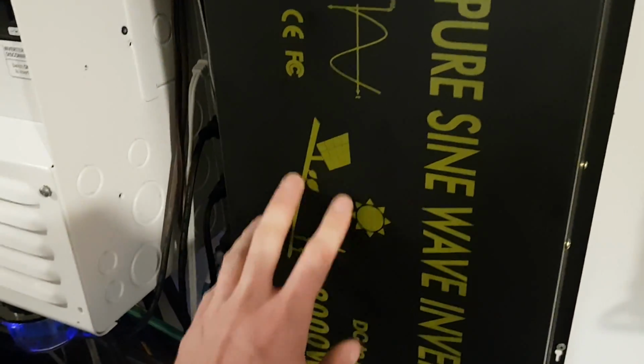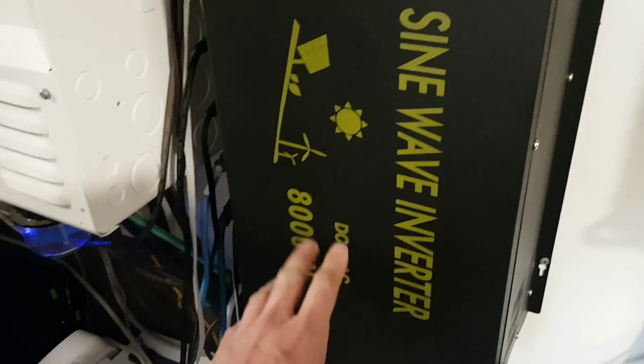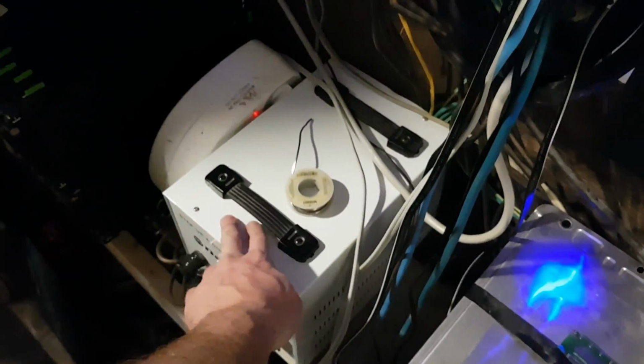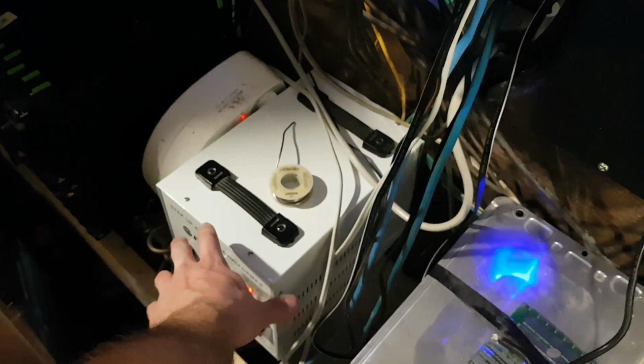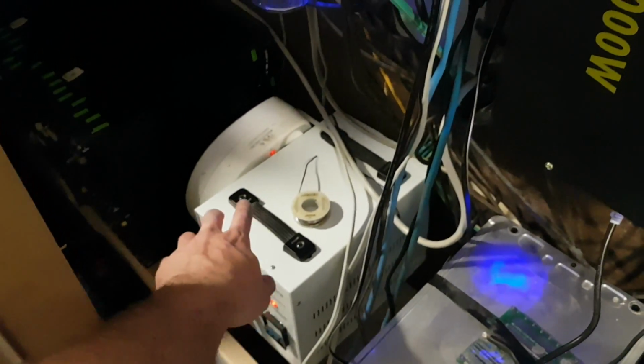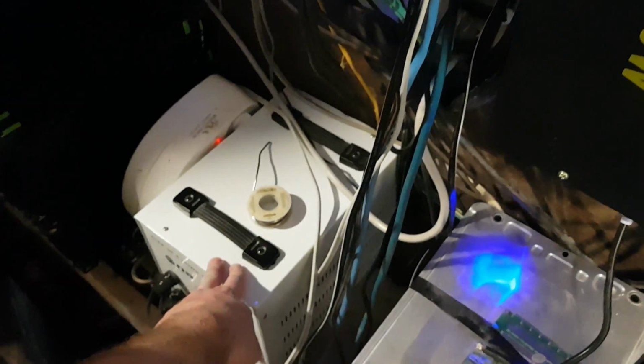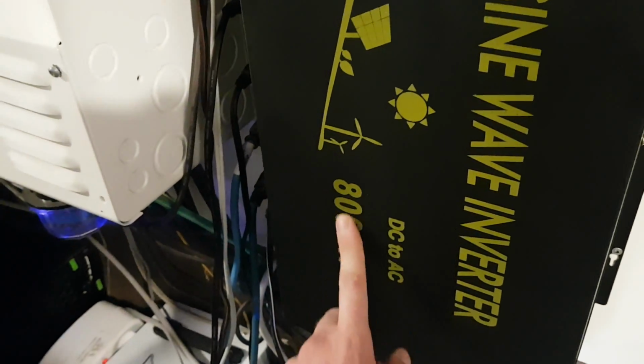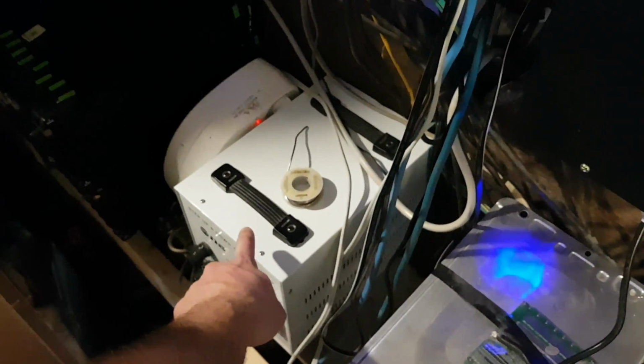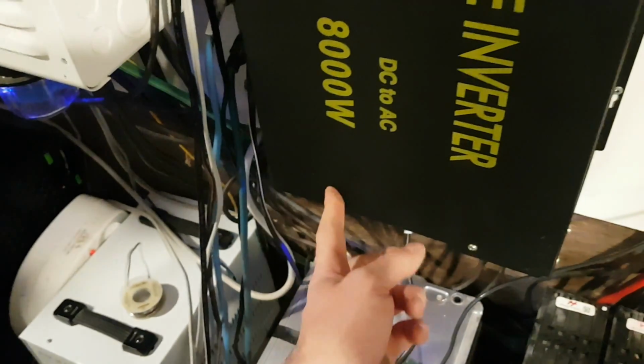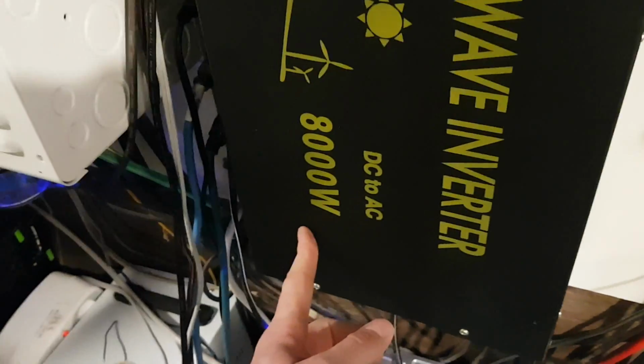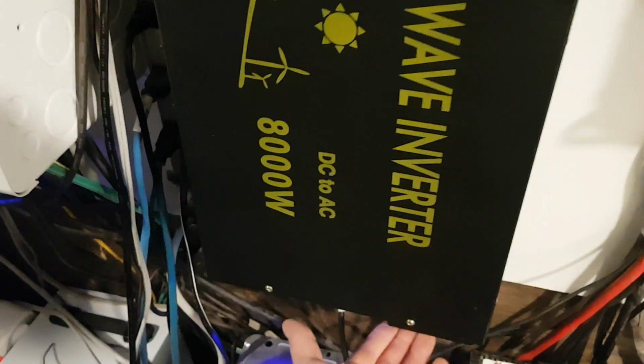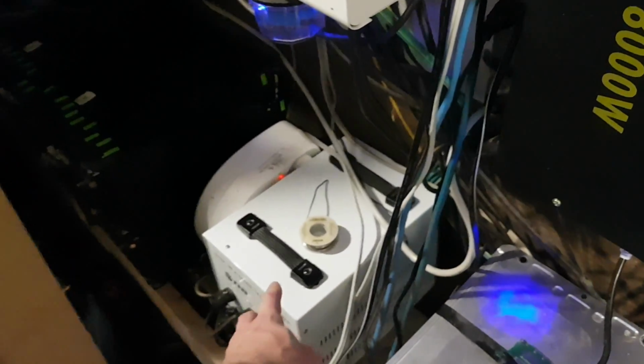So what I've found out so far is I'm able to pull 6,000 watts through this transformer, no problem, out AC. But that's not what this is rated for. So why can I not pull more than 6,000 watts? Well, that's because I'm losing a lot of power in here. At the outlets - sorry, the hardwire - I know you can pull at least 7,000 watts. But I like running through this because it helps with inductive loads and spikes coming back through; the transformer helps clean it out a little bit.